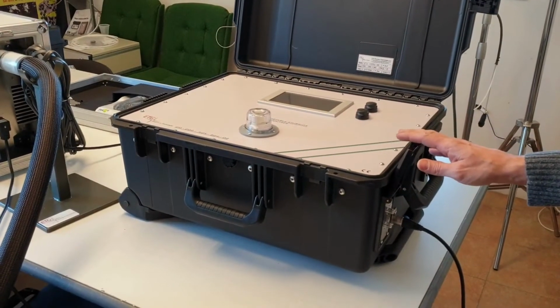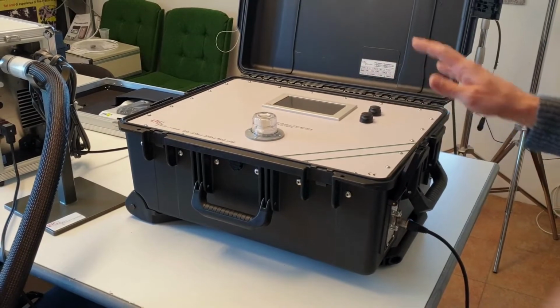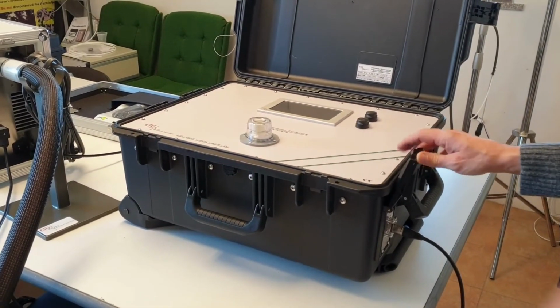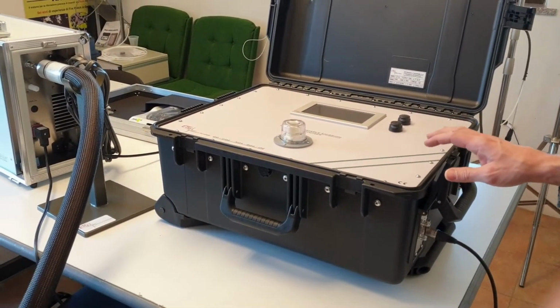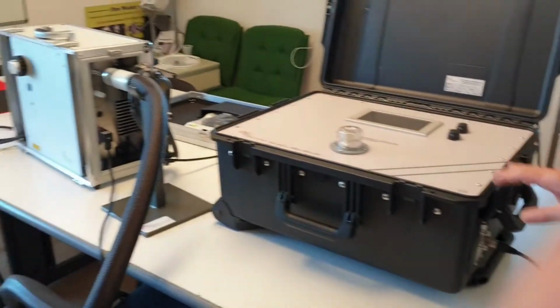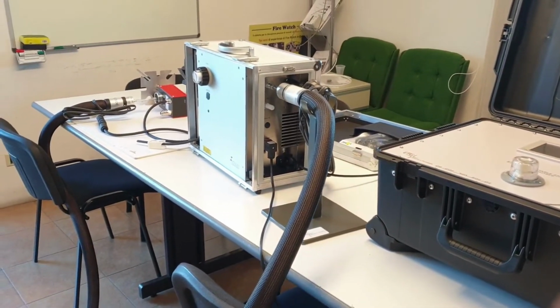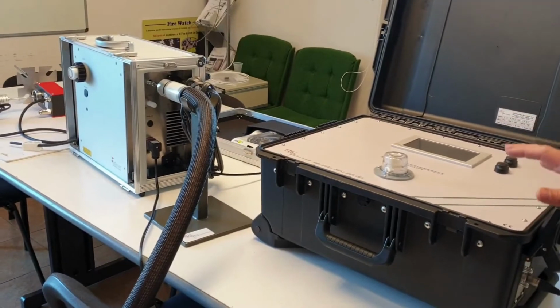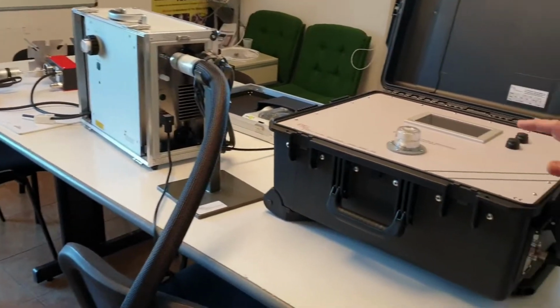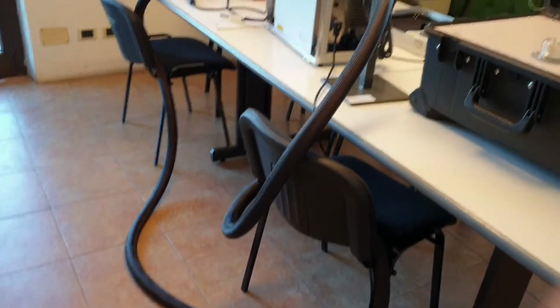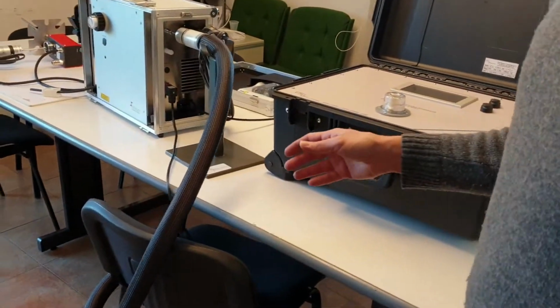After that, before connecting pneumatically the sample conditioning unit and analyzer, it's necessary to switch on electrically all the components and wait until the probe, the heated line and the sample conditioning unit reach the set temperature. We can proceed to switch on.